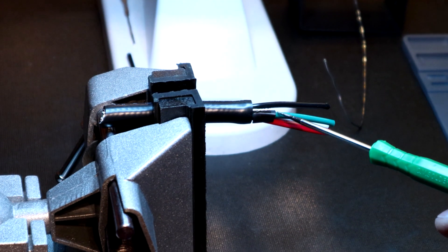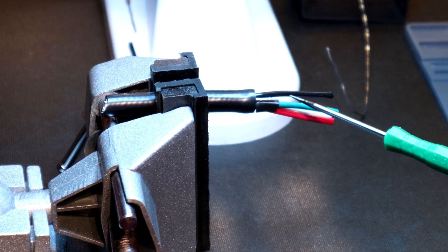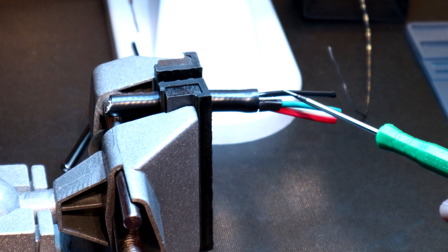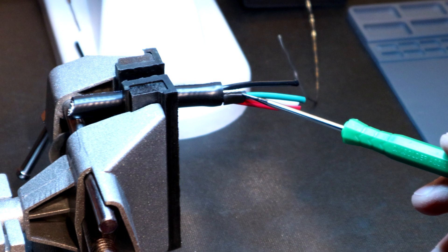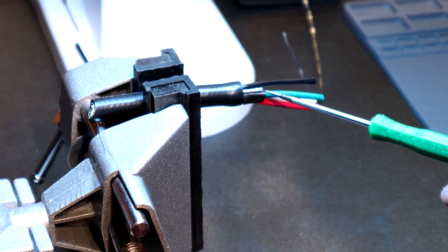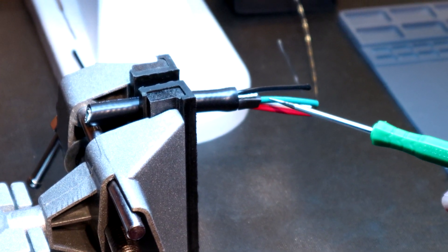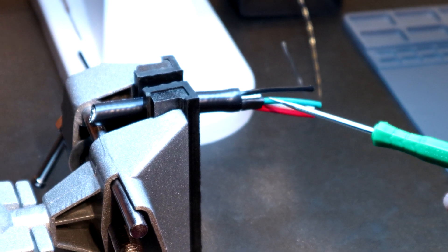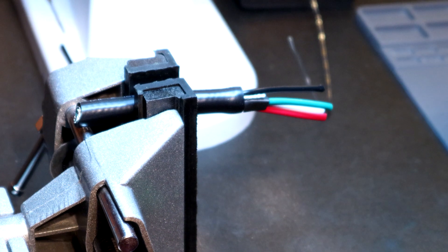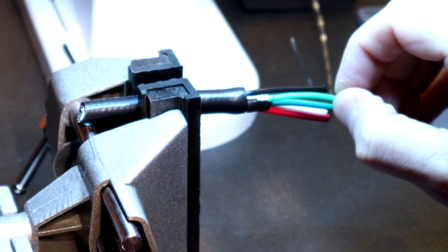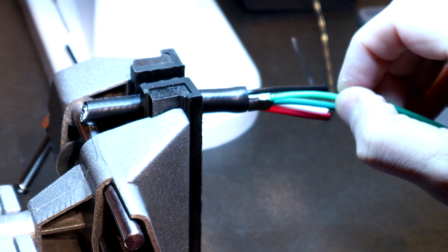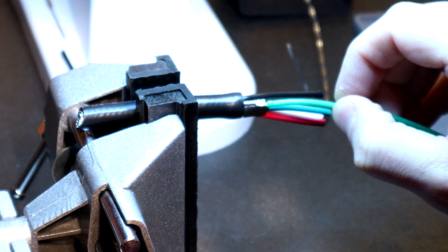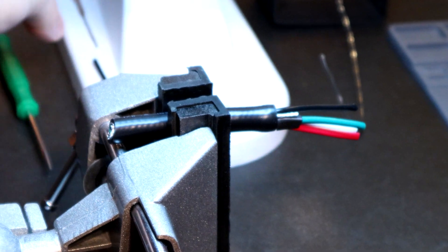And by me applying that, just like I did right there over the ground lead, we know, and actually around in between the ground drain, what we're able to do is diffuse heat because the heat shrink has a much higher temperature rating than the PVC casing in terms of it going to be a polymer shrink. So, we're golden there. Now, what we want to do by doing that is it gives us ample time to apply heat and our flux as well and give us a perfect weld.